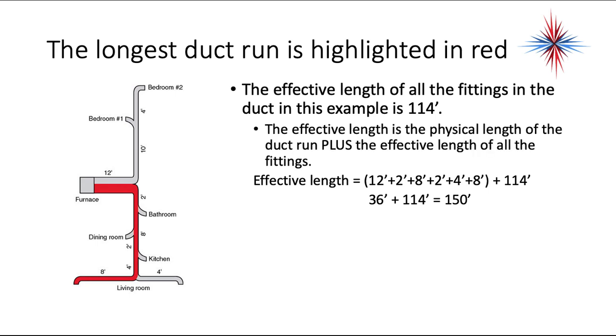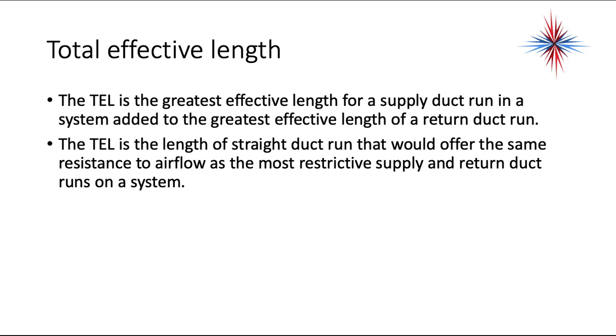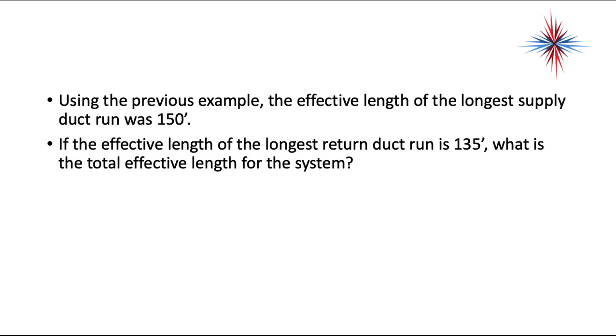The effective length is the physical length of the duct run plus the effective length of all the fittings. The total effective length is the greatest effective length of a supply duct run added to the greatest effective length of a return duct run. In the previous example, the effective length of the longest supply duct was 150 feet and the longest return duct was 135 feet, giving a total effective length of 285 feet.